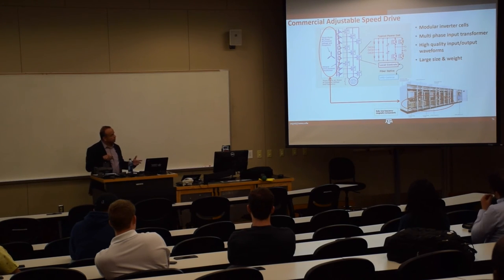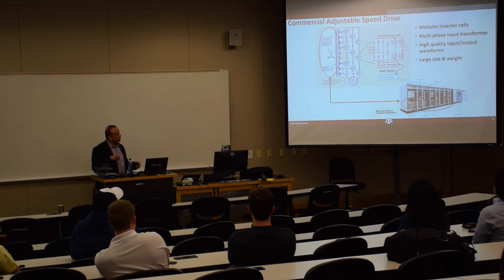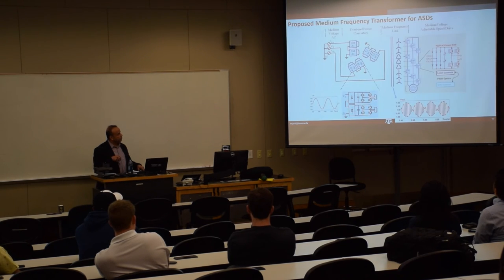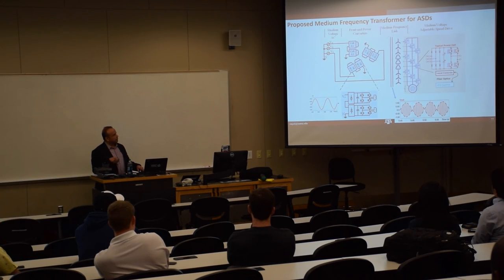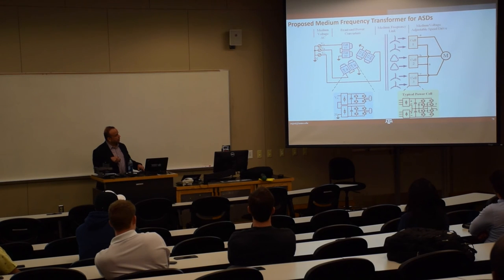Now this concept also works for stacked medium voltage converter drives, where you have different cells in series, and a big 60 hertz transformer with a 60 hertz winding. All you have to modify is this winding, and then the core and everything. Everything on this side remains the same. On this side, all you have to do is modify with stack converters, and on the other side, keep the hardware essentially identical to what you have right now, except that the diodes are working a little bit harder because they have to rectify this one, and then it should be working fine. We are currently looking at a lot of simulations with this one, and if the cell is an NPC, it could be done that way as well.